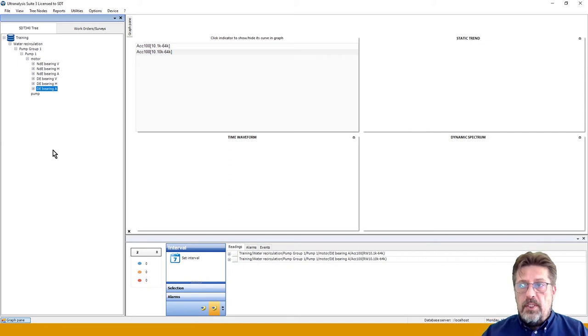Okay, so as you can see, we made a complete setting on a motor. This is one style, as I told you. You can do it differently if you have enough nodes. If you don't have so many branches before, you can divide motor into drive end and non-drive end, and then within drive end and within non-drive end, you can create vertical, axial, horizontal. Of course, if you are not using vibration, it will simplify things a lot in the setting, because you don't need vertical, horizontal, and axial, because you will be doing ultrasound only in one direction, so you need only one point.